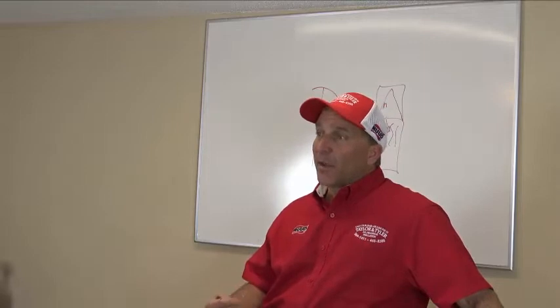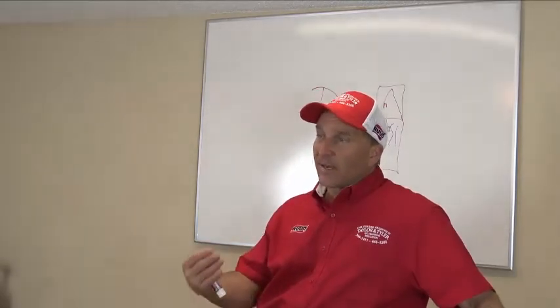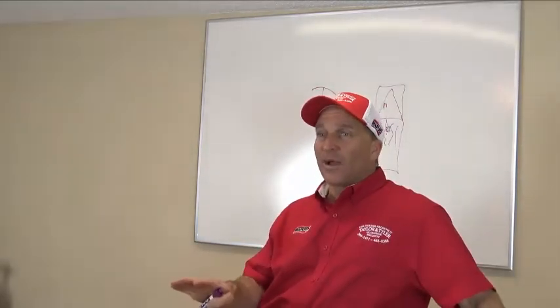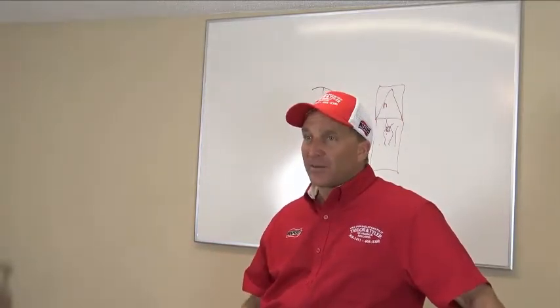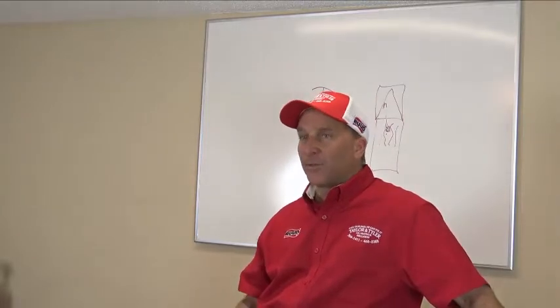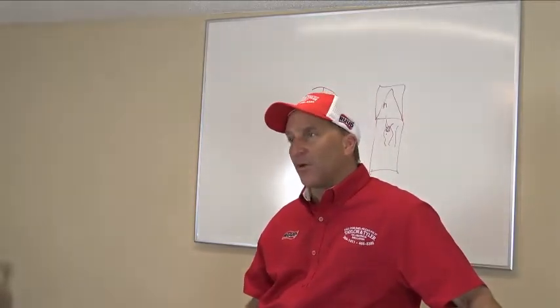So I'm going to recommend go ahead and charge the system up, put that extra refrigerant in. I really don't think you have a leak in the system. Let me ask you, have you had to put refrigerant in this system? I see it's about 8 years old. Have you ever had to put refrigerant in the system? And the guy goes, no.